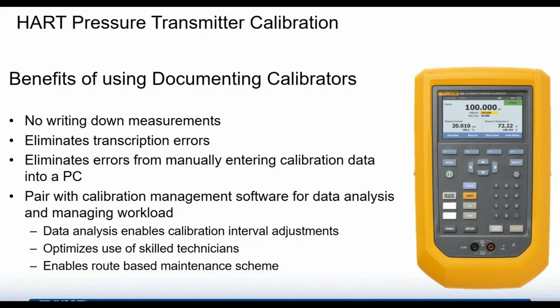It eliminates having transcription errors. I don't know about you guys, but my handwriting's not so good. And if I was to give that calibrator and my test report back to the administrator, they'd have to read my writing. So that makes it difficult. So yeah, you don't have to manually enter that data into a PC because it automatically uploads. So pairing a documenting calibrator with management software optimizes your time, and it allows auditors to have that information available, to look at those test results. It's all documented for you.